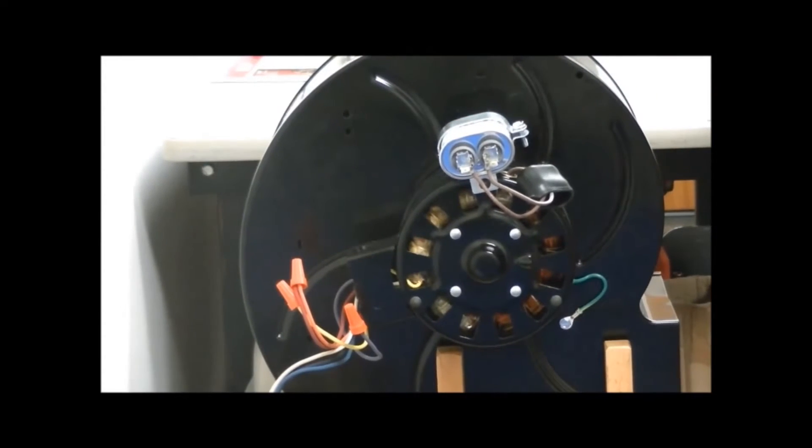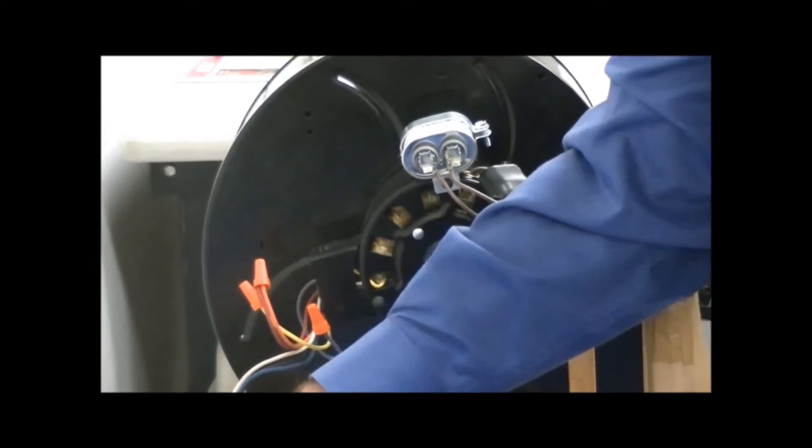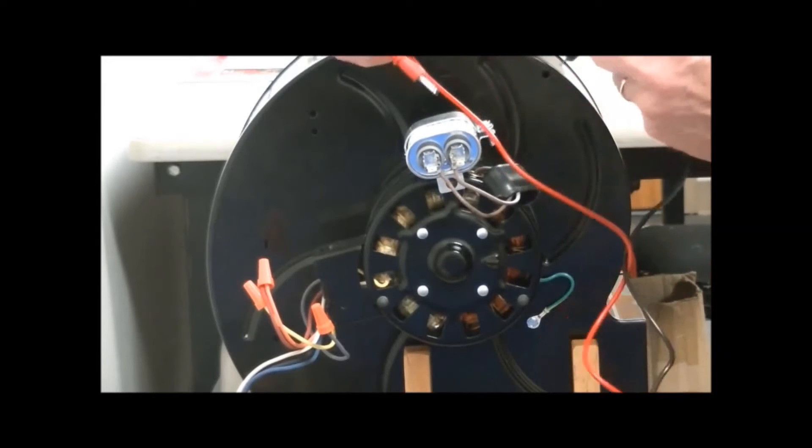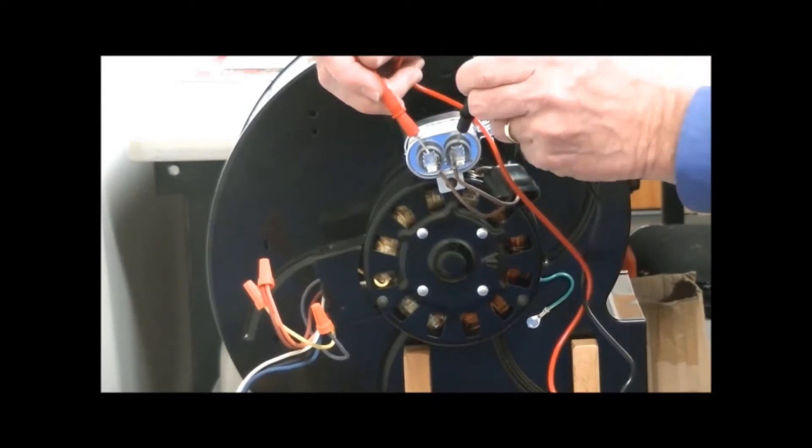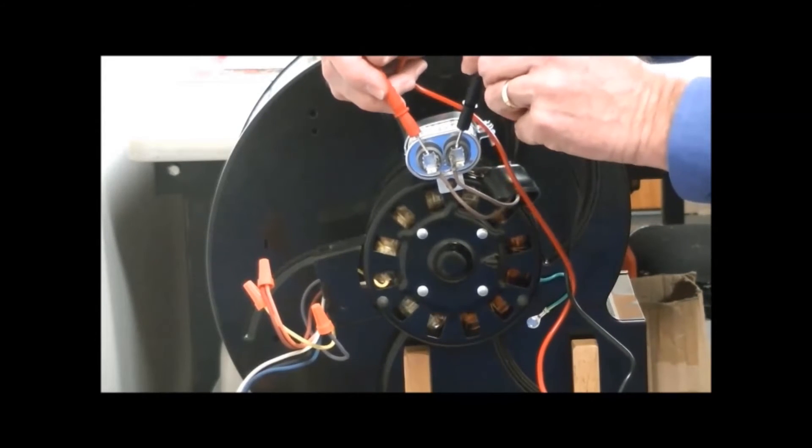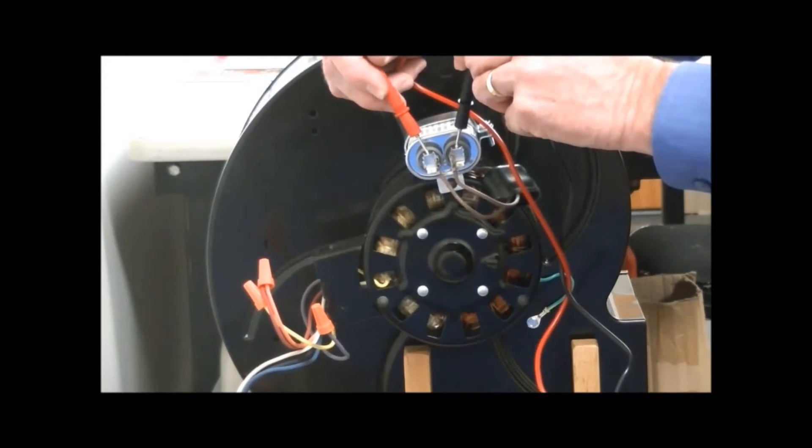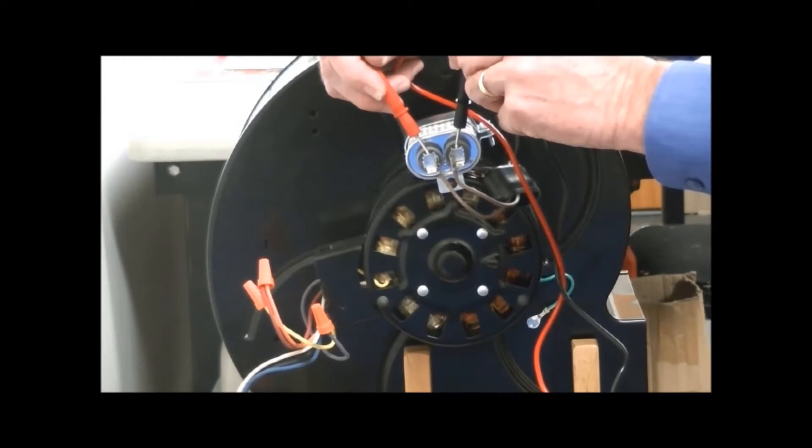In this case here, we will check the volts first, the capacitor volts. To do that, one probe on one side, the other probe on the other. The capacitor volts, in this case, are 318.